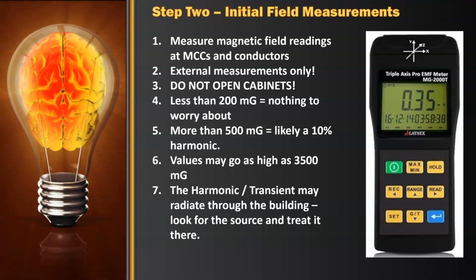Less than 200 milligauss, nothing to worry about. You probably have 5% harmonics or less, not worth chasing down. More than 500 milligauss, there's likely a 10% harmonic, maybe as much as 15%. And you may see values go up to 3,500 milligauss. That's very problematic. Not going to be harmful to your health. You're not going to grow an extra arm or anything like that if you're around it. But 3,500 milligauss is indicating that there's a serious harmonic or transient problem.